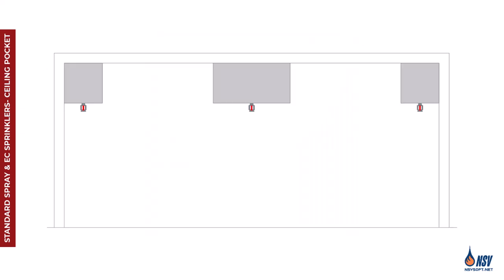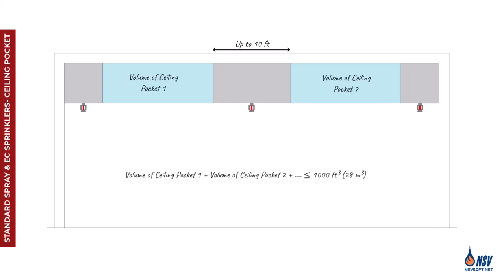Finally, it's important to note that when multiple ceiling pockets are located within the same compartment and are within 10 feet of each other, NFPA 13 requires their combined volume not to exceed 1000 cubic feet. All other conditions such as the maximum depth, non-combustible or limited combustible finishes, and full floor coverage from the lower ceiling level must also be satisfied for sprinkler omission to be permitted.